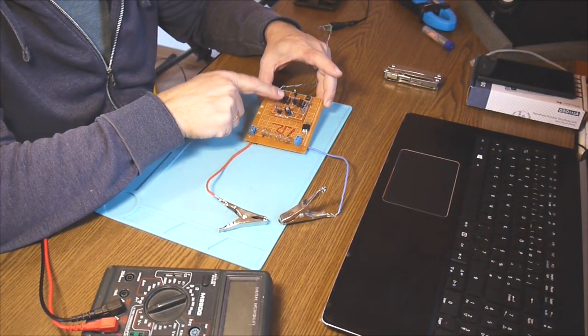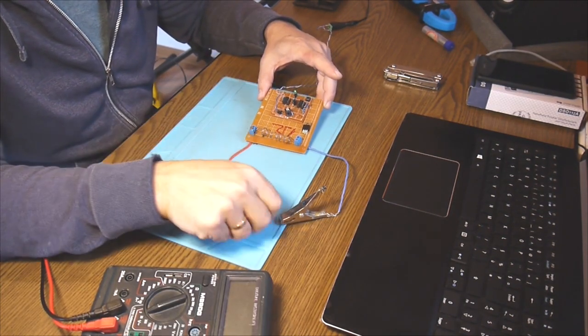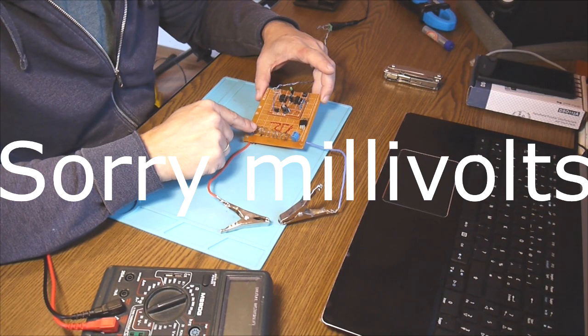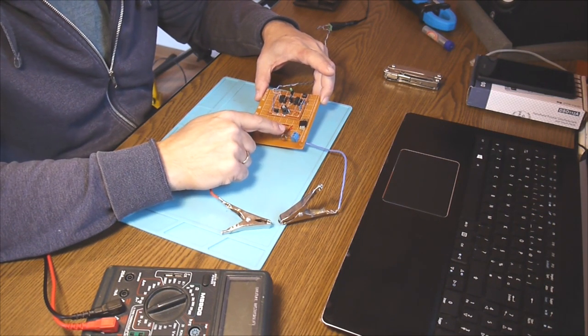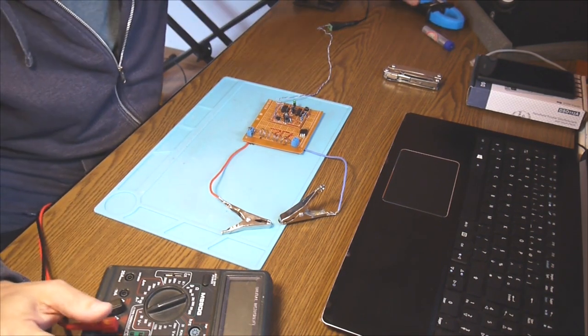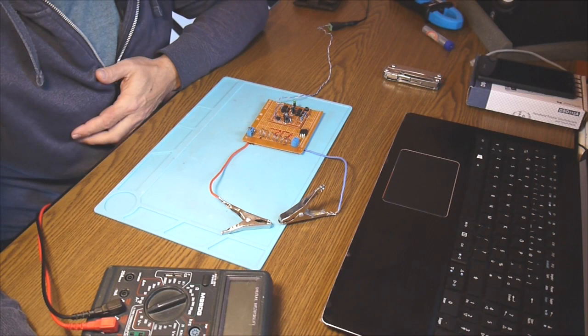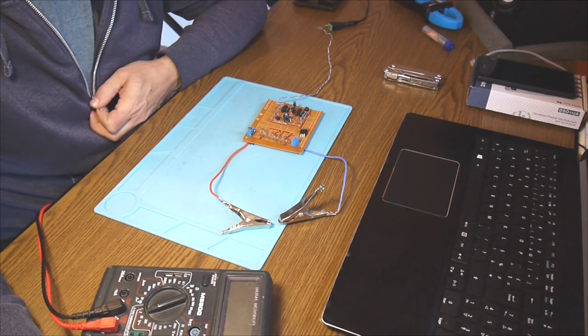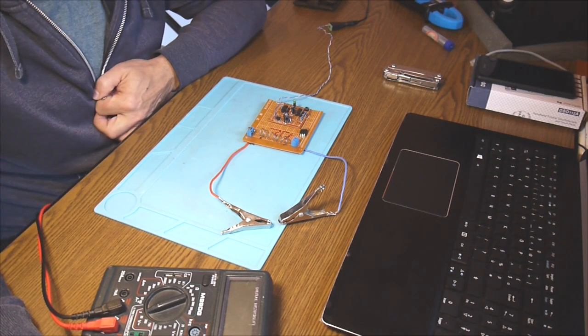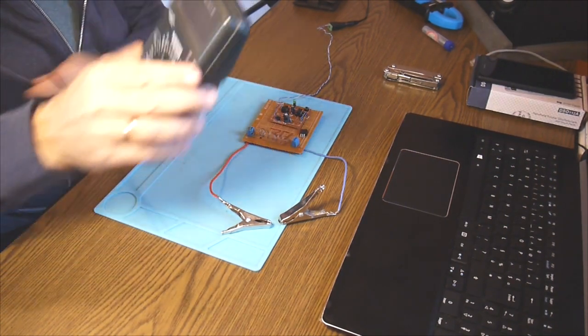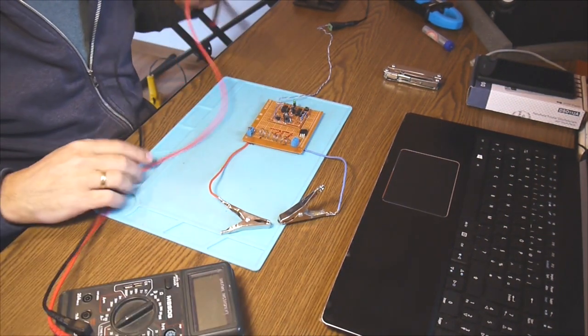These are working properly for 50-60 Hertz alternating current. One is applying the load to the battery terminals for about 10 seconds. We'll have a voltage fall on this resistance here and I can measure that in millivolts. Afterwards that will be divided by 10 and it gives me an idea of the internal resistance.